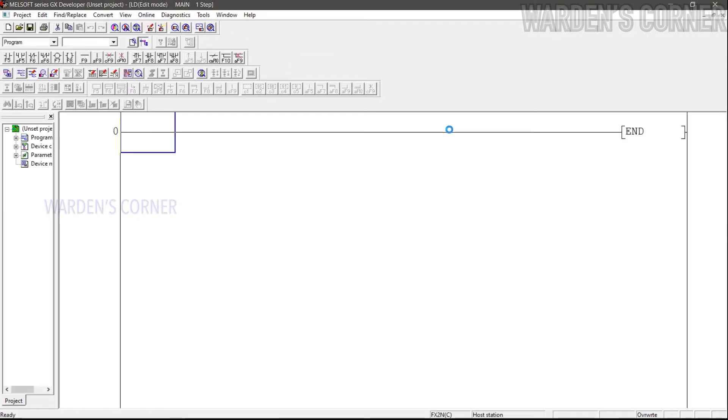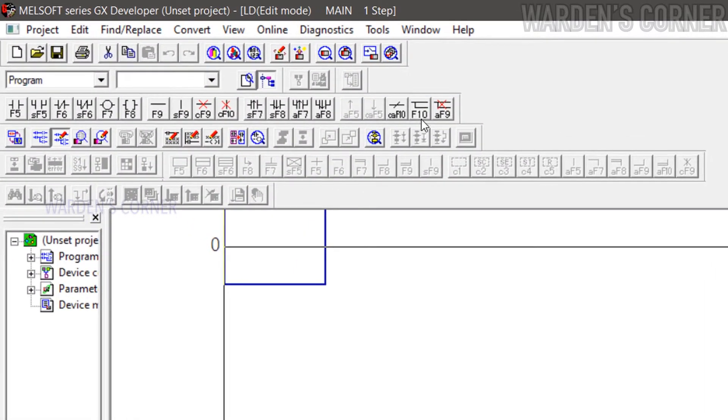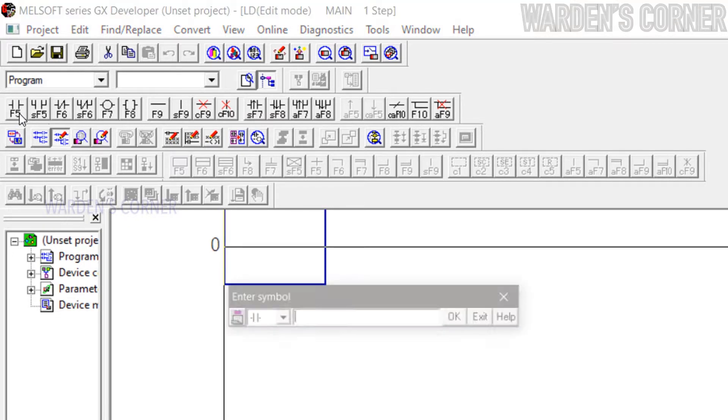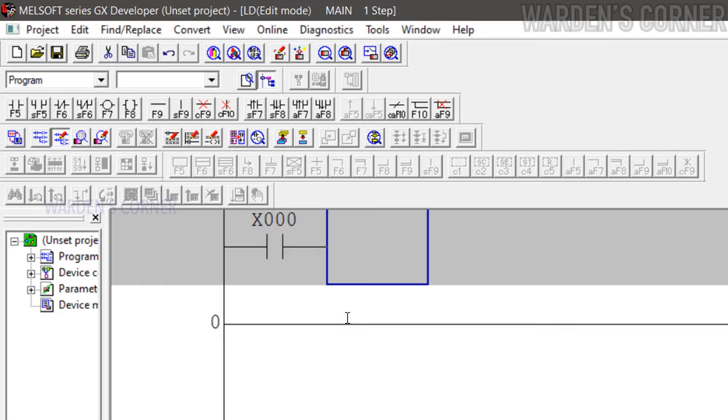The programming display for ladder logic will appear. These are the input and output programming icons to be used. We will create a simple logic program, start-stop control. Click Normally Open Contact or press F5, type X0. X is the prefix code for input devices. X0 will serve as the start push button.